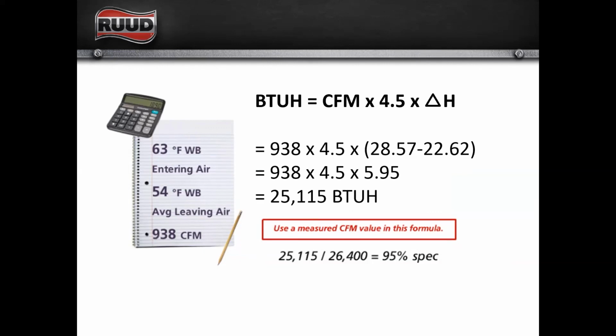Then you're going to do the math, and that's going to give you 25,115 BTUs per hour. So right now we measured the amount of heat that we're moving from this system. This matchup is specified at 26,400 BTUs per hour. We're moving 25,115. We're at 95% of specifications. Honestly, we can't expect this piece of equipment to be operating any better than this, right? 95% spec is fantastic.